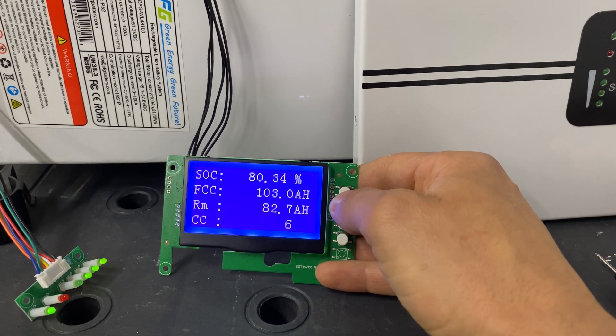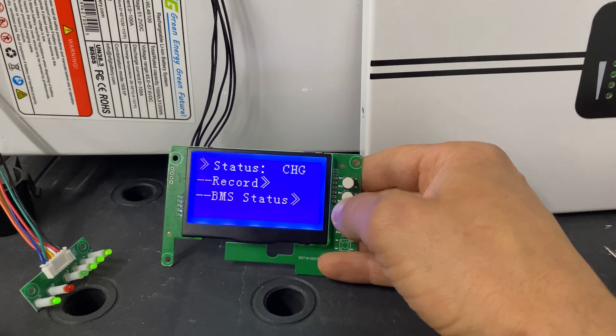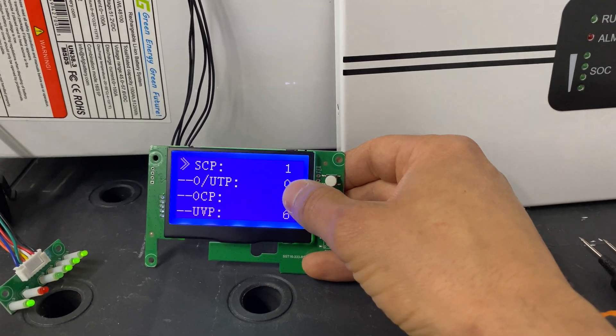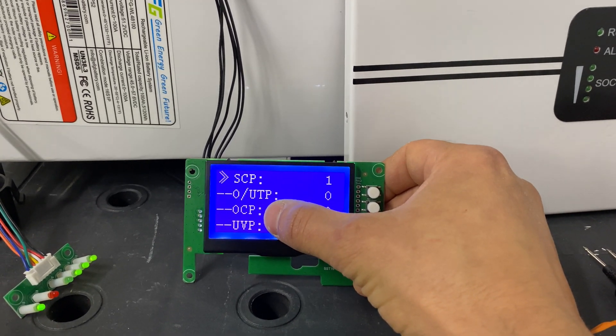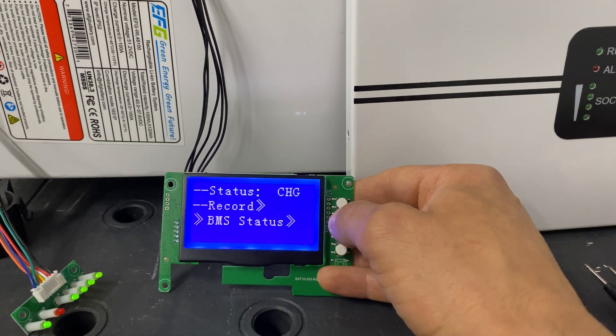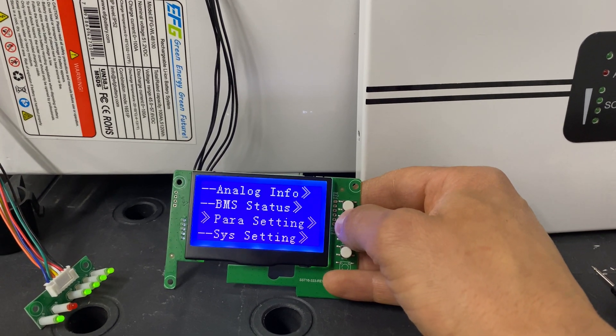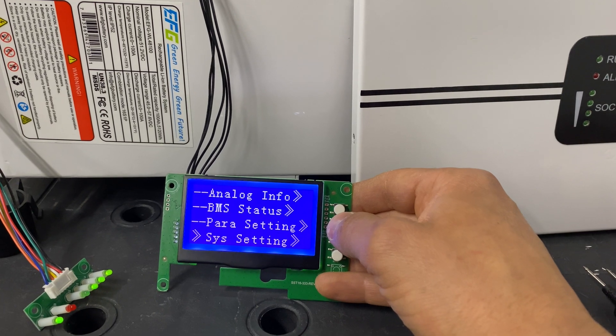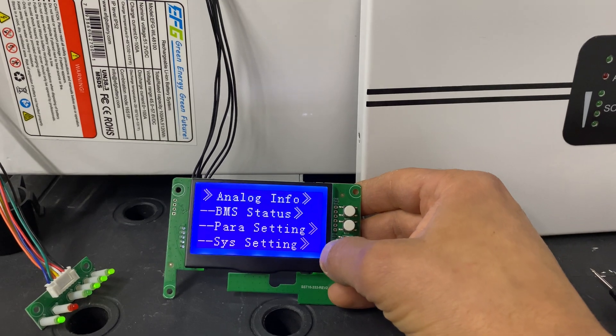Then we can see individual cell voltage for all 16 cells. In cell capacity we can see state of charge, amp hours, remaining capacity, and cycle count. On the BMS status we can see if it's charging. On the record screen we can see if any protection has happened — short circuit protection, over and under temperature, over current, under voltage, and over voltage. Parameter settings and system settings show communication speed. That's all the information available from this screen.